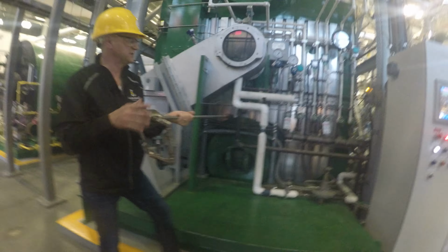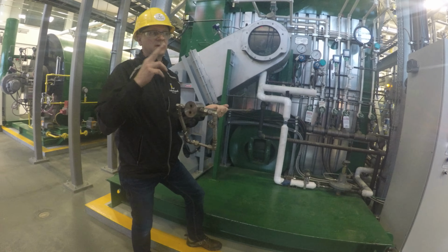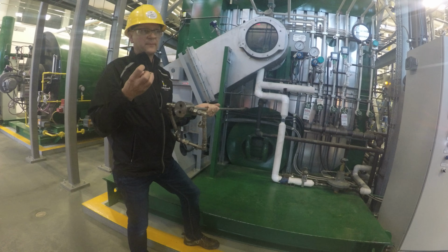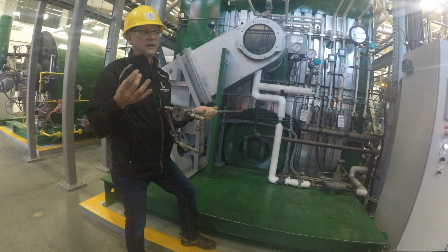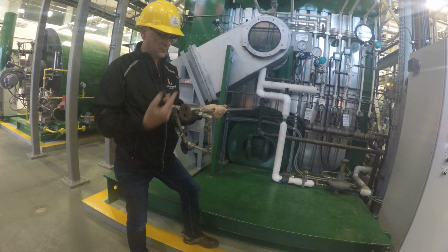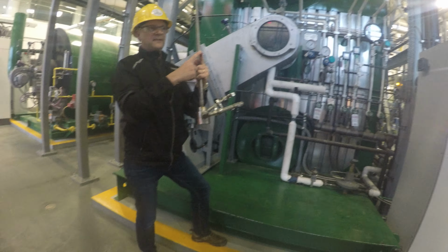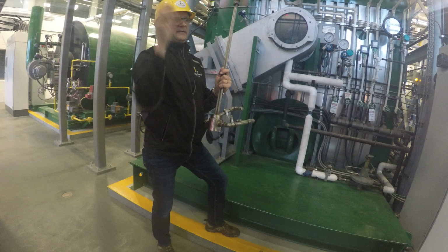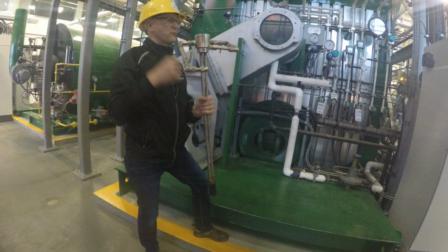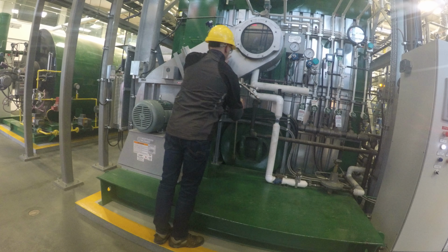To atomize the diesel fuel, the oil, we'll use either compressed air or intermediate steam. We actually have three steam systems here: a high pressure system, a low pressure steam header, and an intermediate, which is about 700 kPa. One of these lines will bring in steam, the other will bring in oil, and we'll send them down to this gun. This nozzle takes the two jets, one of oil, one of steam, and mixes them and atomizes the oil, and boom, you throw a match to it and you've got a fantastic burn. These things burn incredibly clean with steam, way better than compressed air. It's amazing how it works.